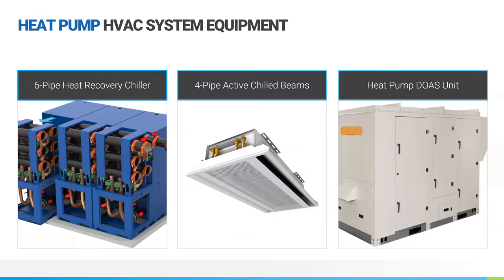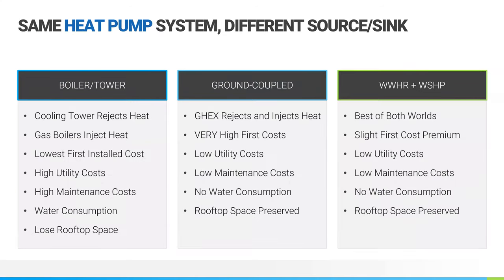So these systems did not change. It was a heat pump HVAC system, no matter which route they were going, they were just changing what was going to be providing the hot or the warm source of heat, or the heat rejection to that heat recovery chiller. So that's where they had either boiler towers or a ground source system or the wastewater heat recovery system. So they weighed all three of those options out. With the boiler tower, you've got your cooling tower that's rejecting heat during the summertime. Boilers are injecting heat during the wintertime. It does have the lowest first installed cost.